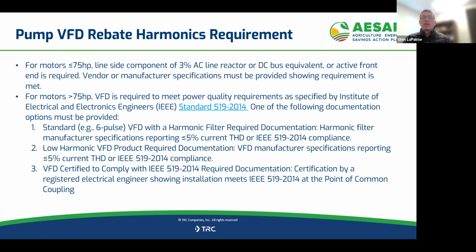Or manufacturers also sell low harmonic VFD products that are manufactured to meet that requirement. Or, to truly comply with IEEE 519, you would need a certification from a registered electrical engineer showing that at the point of common coupling, the harmonics meet the specific requirement for that system.